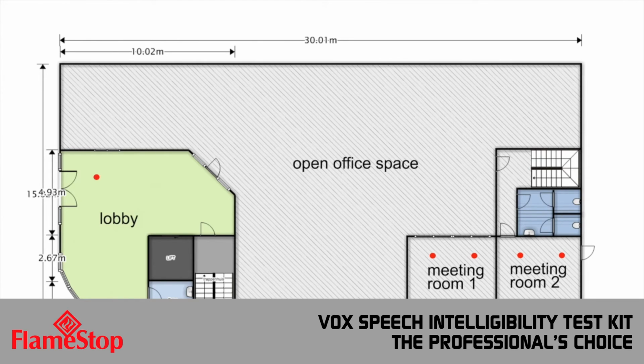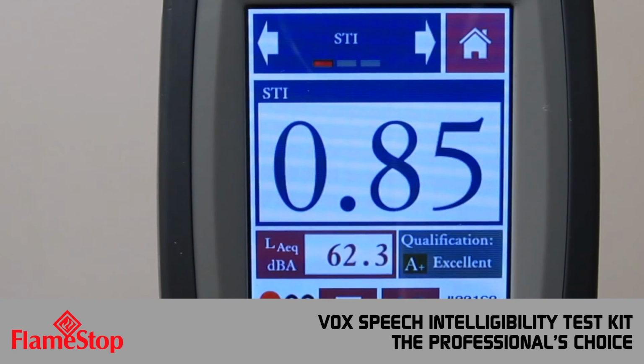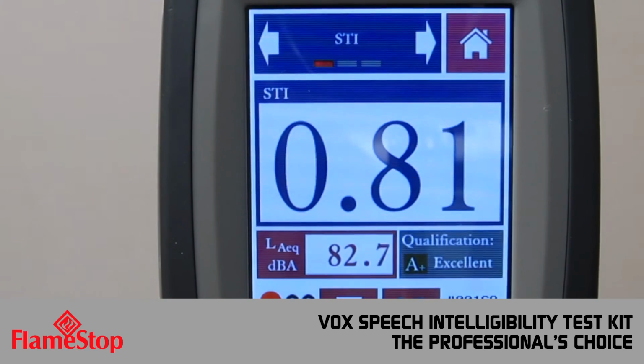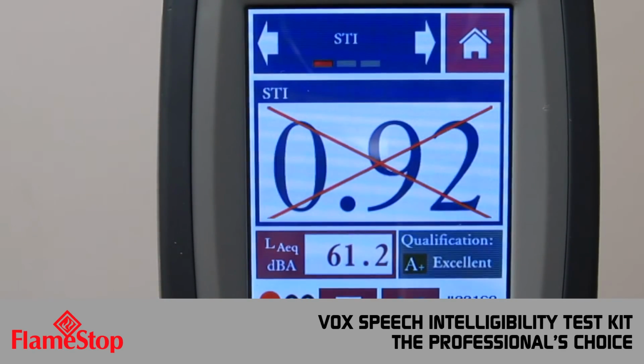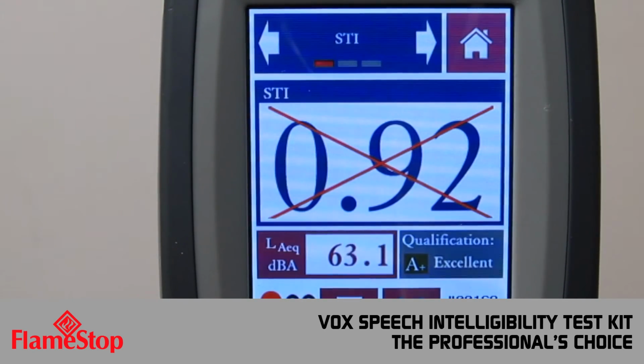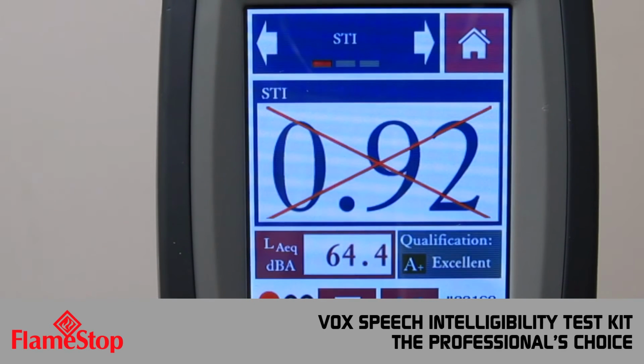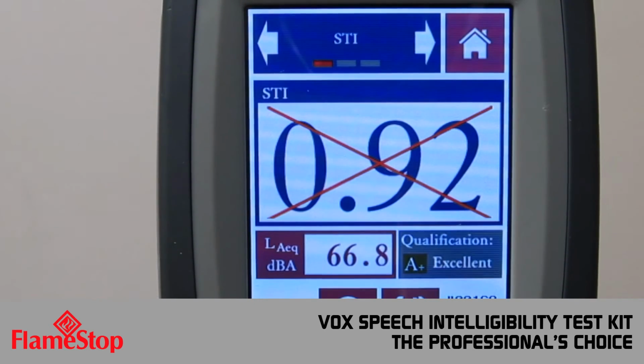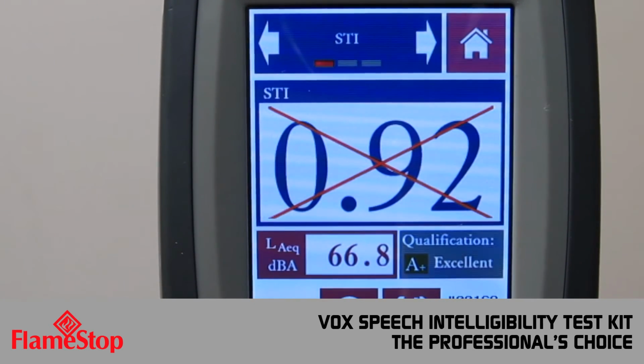Before conducting any tests, please review your relevant standards and any existing baseline data to determine where the reference points will be. The STIPA method does not deal well with impulse noises such as slamming doors. If this happens, discard the measurement and start a new one. If the analyzer detects an invalid measurement, the STIPA result will be crossed out.